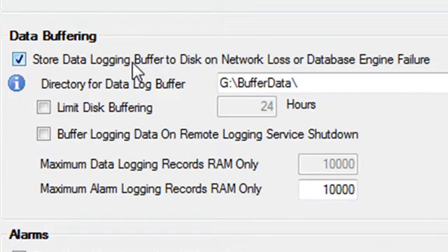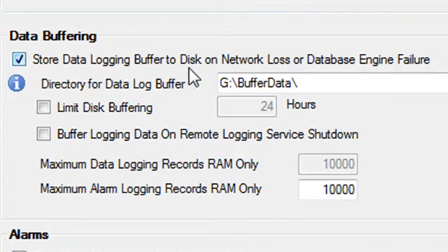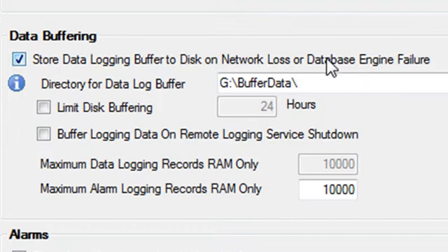To enable data buffering, it's very simple. Just select the property called store data logging buffer to disk, on network loss, or database engine failure. Then specify a directory where you would like the data buffer files to be stored.